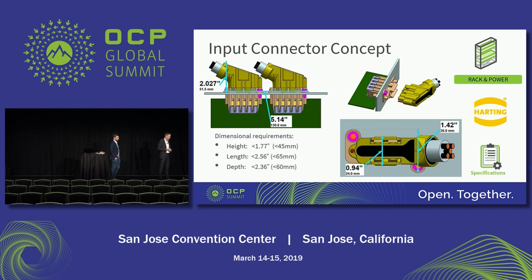Sure. So from Facebook's standpoint, and you kind of alluded to this as well, if it's a direct wire interconnect to the back of the power shelf, then it normally would require an electrician to make that interconnect, as opposed to a lesser trained technician that's building this. We don't have to have a certified electrician do that hardwiring. That would have to occur in the data center, so we'd have to have a data center technician, at least for us. If the rack gets delivered with just terminal blocks, those wires would have to be terminated by an electrician. Instead, the guy rolling the rack into position can just take the cable and plug it in because it's connectorized like this. So that's the value of the connector: you don't have to have a certified, licensed electrician put those wires in.